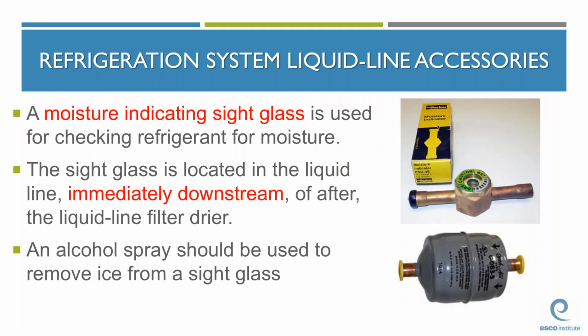Some systems are equipped with moisture indicating sight glasses. These moisture indicators are located downstream or immediately after the liquid line filter dryer. When the moisture indicator, which is typically a colored dot, changes color, often from green to yellow, the system contains excessive moisture. In this case, the moisture issue must be addressed and the filter dryer must be replaced. Stress to your students that anytime the system is open for service, the filter dryer should be replaced.